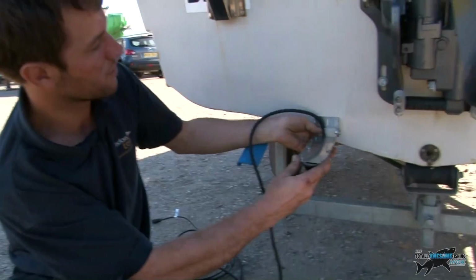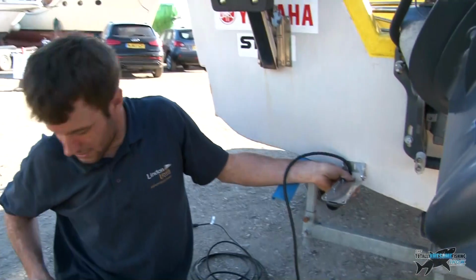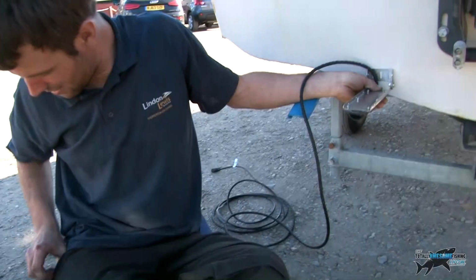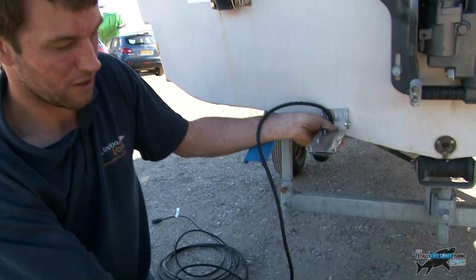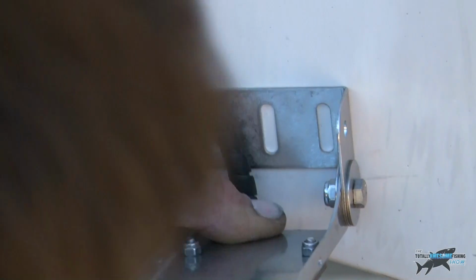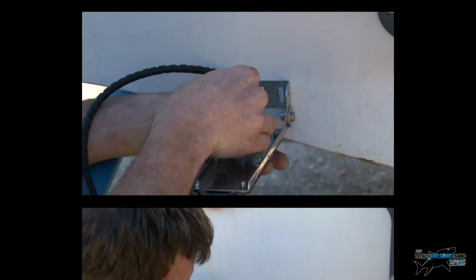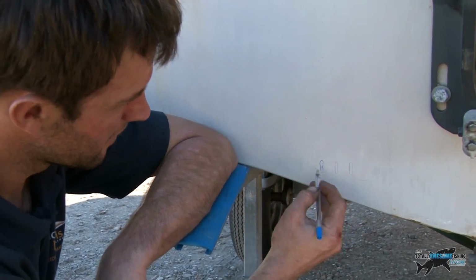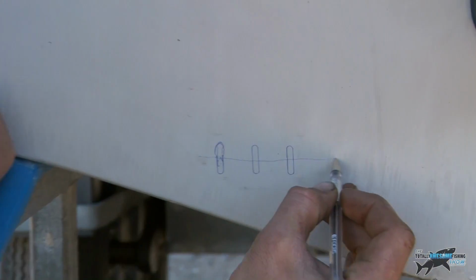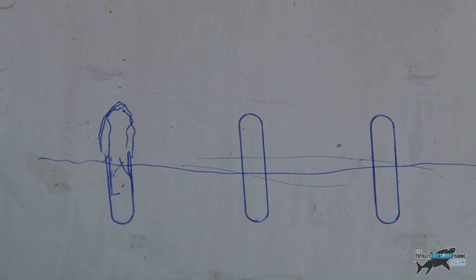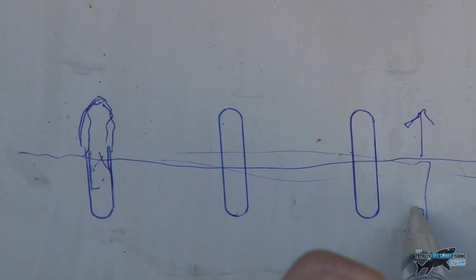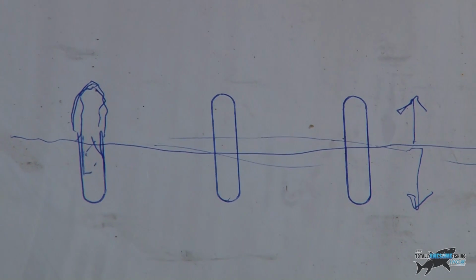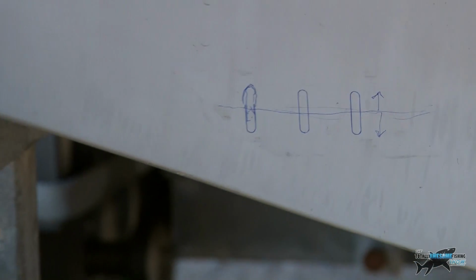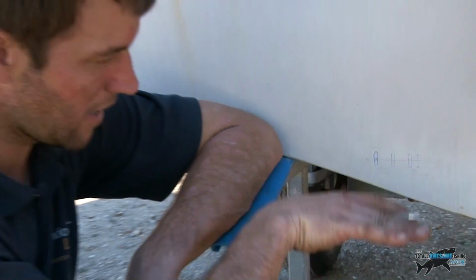Now, there's a couple of different ways to do this. Obviously the slightly nicer way to do it is with a pen or a pencil. Pencil's really good for fiberglass because you can just wipe it off and start again. Alright, so the idea with these slots are we're going to install our screws along that level there. That's going to give us the ability to come up or down over about 20 mil. So if we have got the transducer too high, transducer too low, we can fine tune it.